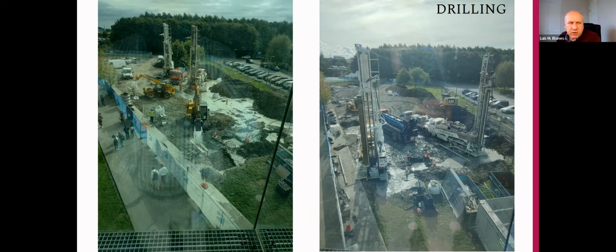So it's always very important to have this core retrieved. And I also recommend for large investments to also have one test borehole where you can also do a heat extraction test, or a thermal response test, a heat injection test. It eases a lot all the decision making with all the uncertainty of the ground.